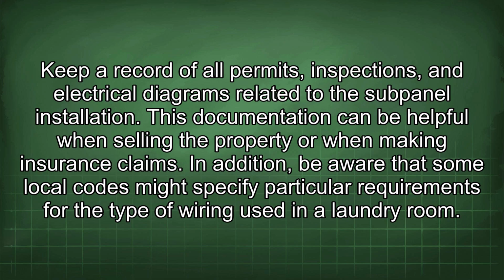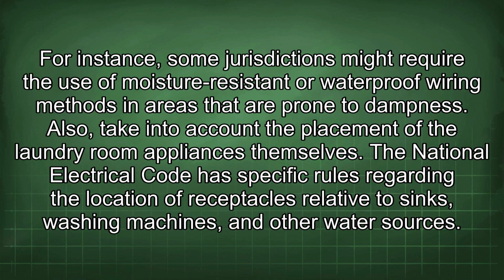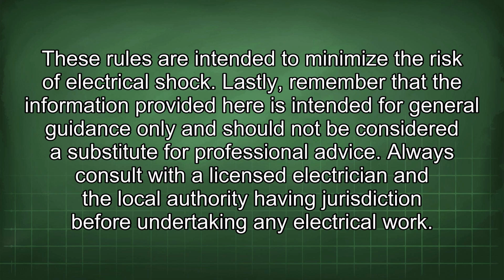In addition, be aware that some local codes might specify particular requirements for the type of wiring used in a laundry room. For instance, some jurisdictions might require the use of moisture-resistant or waterproof wiring methods in areas that are prone to dampness. Also, take into account the placement of the laundry room appliances themselves. The National Electrical Code has specific rules regarding the location of receptacles relative to sinks, washing machines, and other water sources. These rules are intended to minimize the risk of electrical shock.